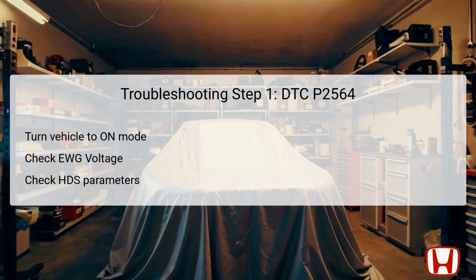The expected value should be at or below 0.16 volts. If the values fluctuate above this threshold, this may suggest an intermittent failure or an issue with the components involved. If the current conditions match the parameters, it is advisable to move to Step 2 for further diagnosis.